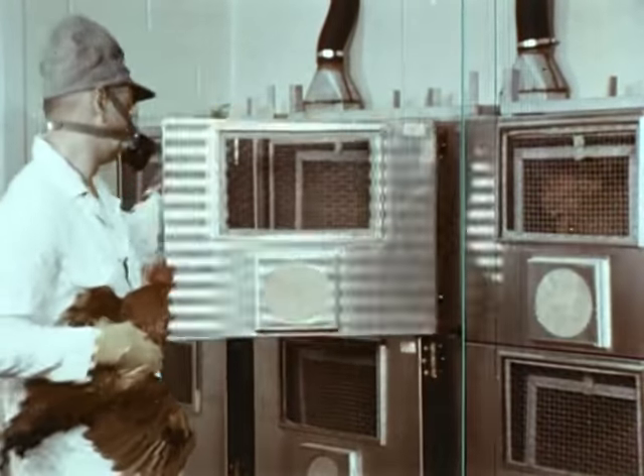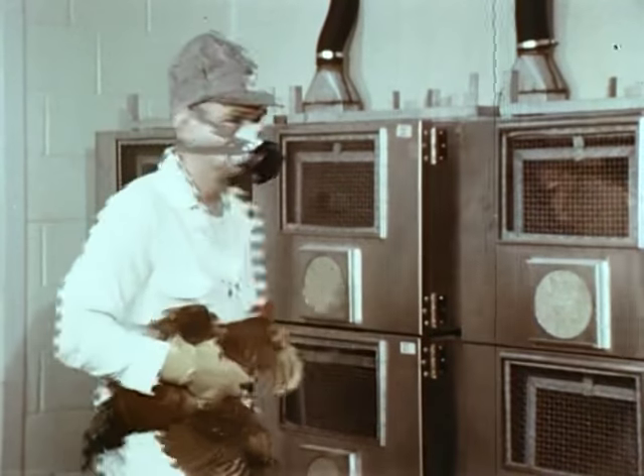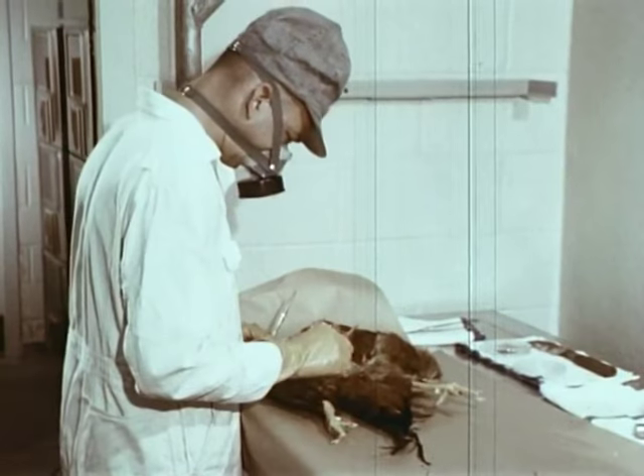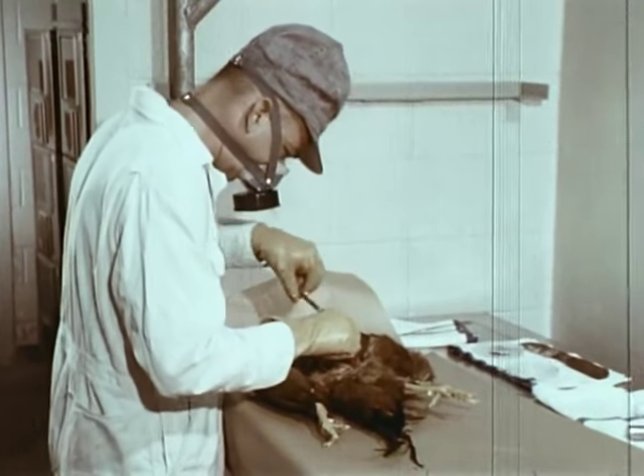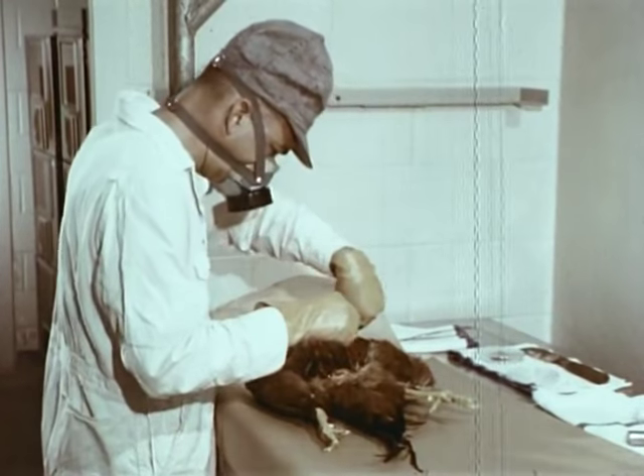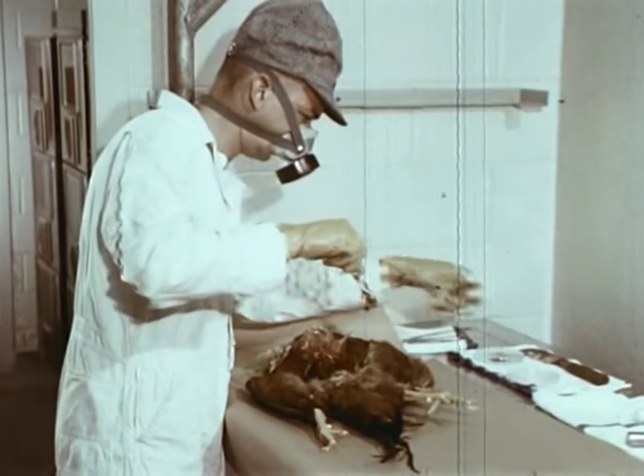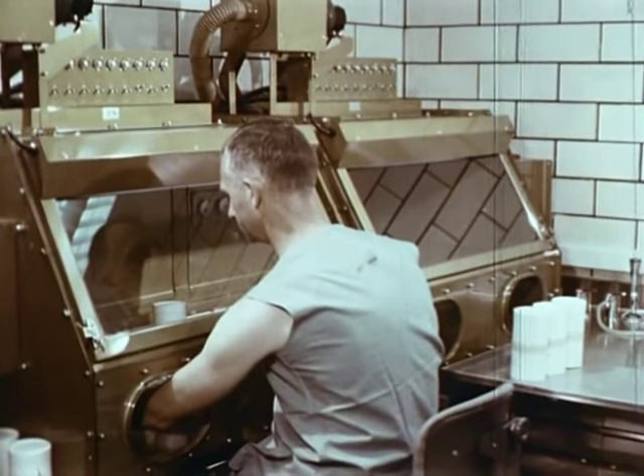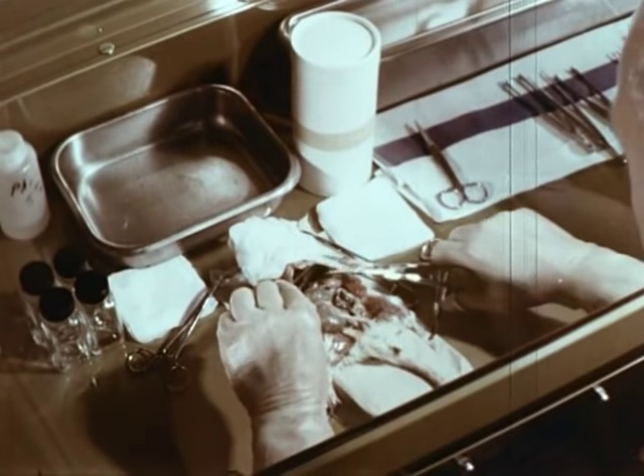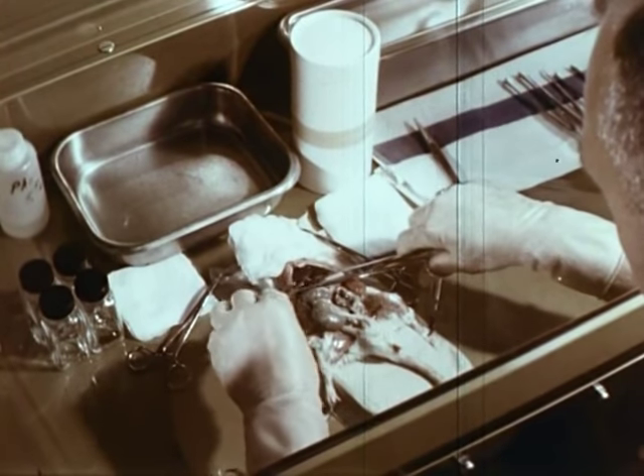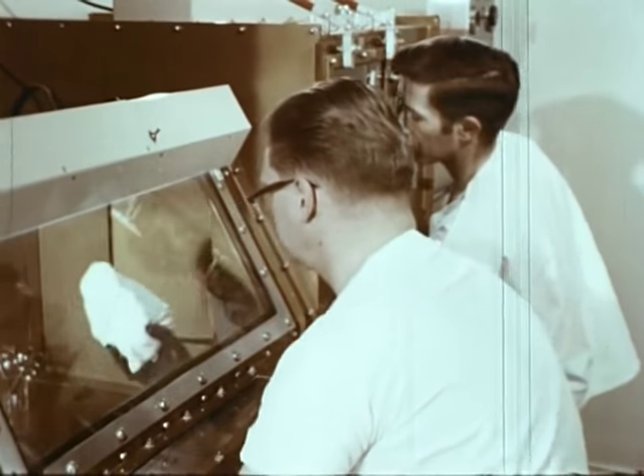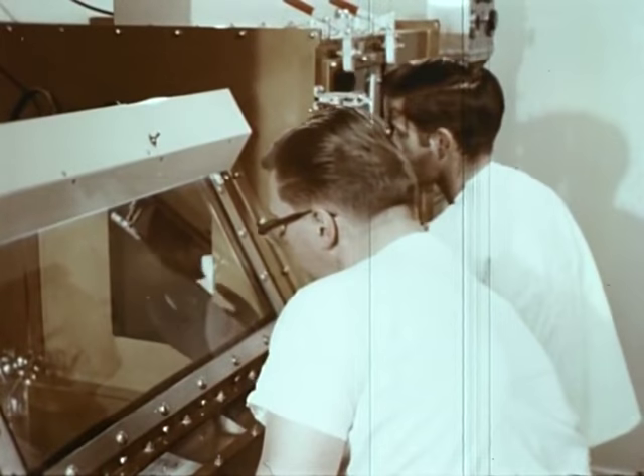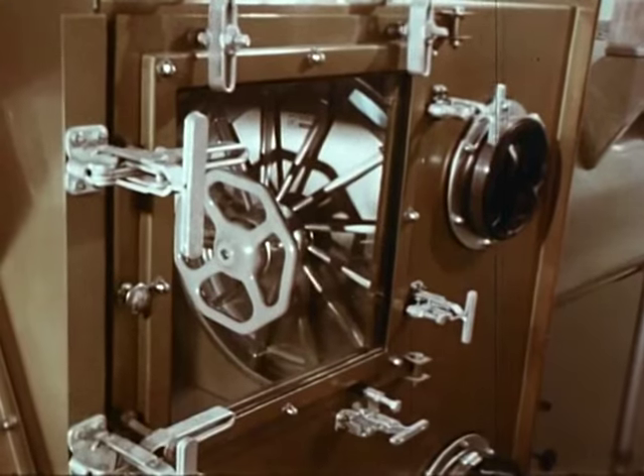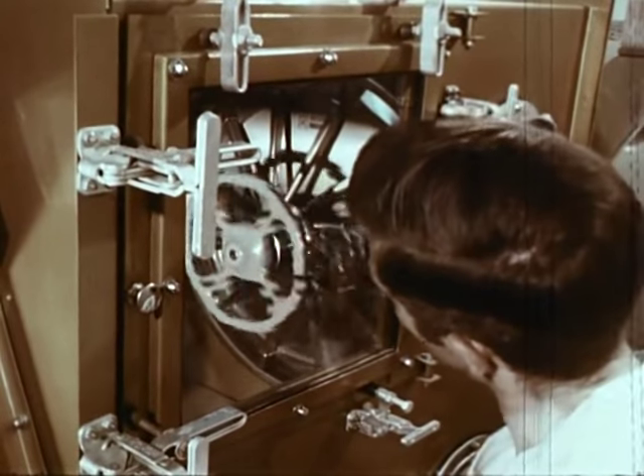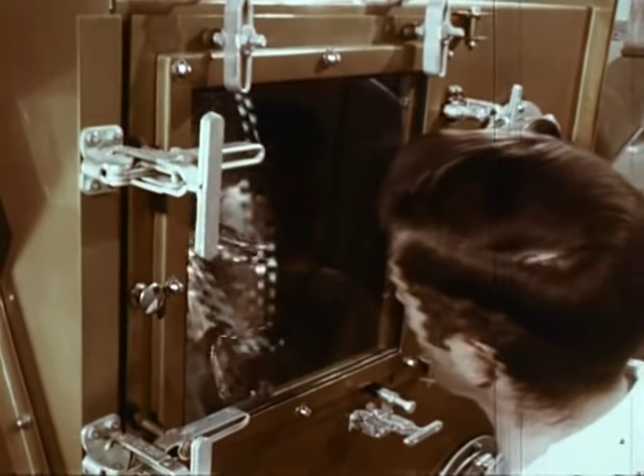It is convenient to locate small animal holding rooms close to rooms where inoculation and autopsy are done. With disease agents of low hazard, tabletop autopsy is permitted. In this case, the operator should wear a respirator. For higher hazard work, animal autopsy should be done in ventilated safety cabinets, where an inward sweep of air prevents the accidental escape of infectious aerosol. Where maximum protection is required, an absolute barrier cabinet system with attached rubber gloves must be used. This cabinet is equipped with an autoclave for sterilizing animal carcasses and other materials removed from the system.